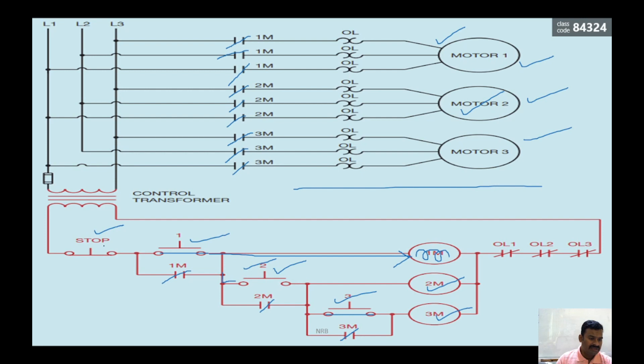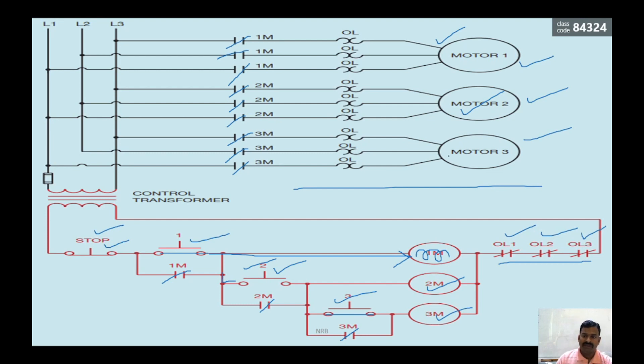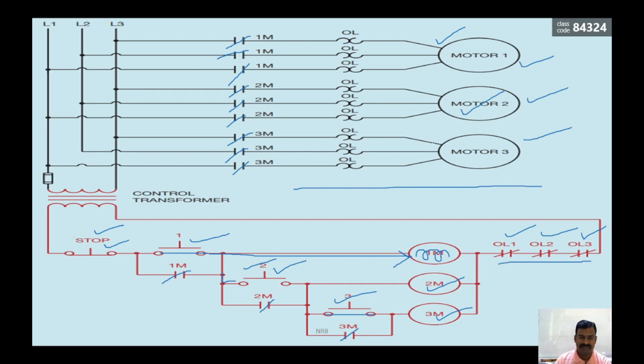When you want to turn off the machines at any point you can operate the stop switch, or if any one of the motors is getting overloaded, that particular overload relay is going to open its contact so that all the motors turn off simultaneously. So this is the relay logic for this sequence — the three motors run in sequence: first motor, second motor, then third motor.